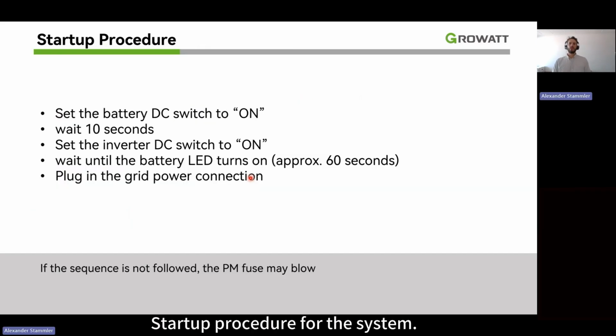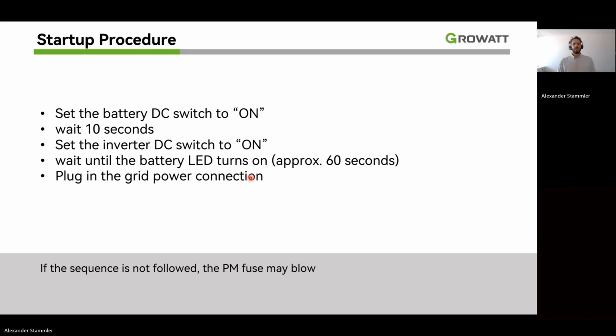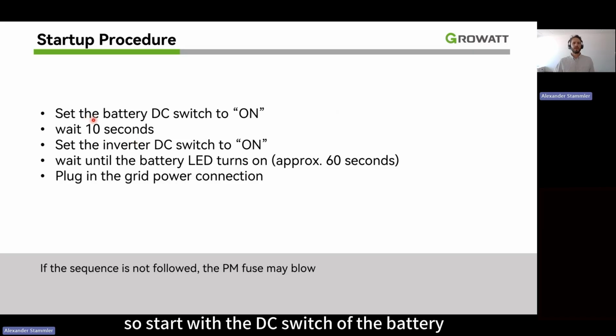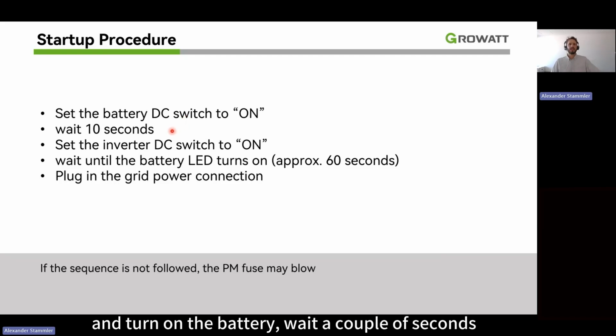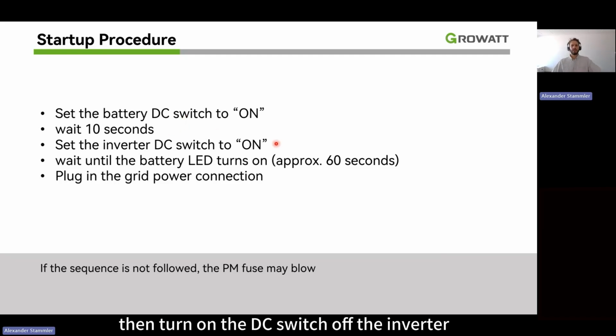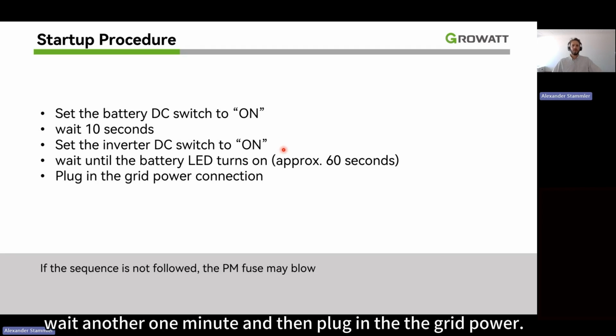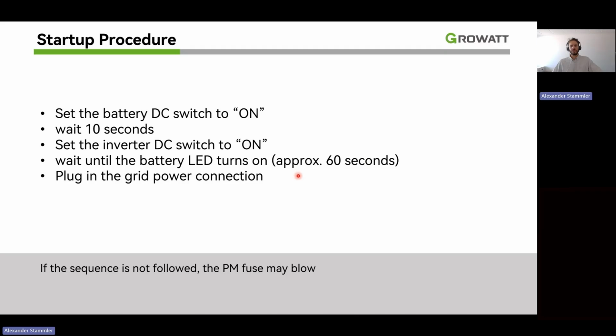Startup procedure for the system. If it's all off, start with the DC switch of the battery and turn on the battery. Wait a couple of seconds, then turn on the DC switch of the inverter. Wait another 1 minute, and then plug in the grid power for the inverter. This is the best way to start the system.